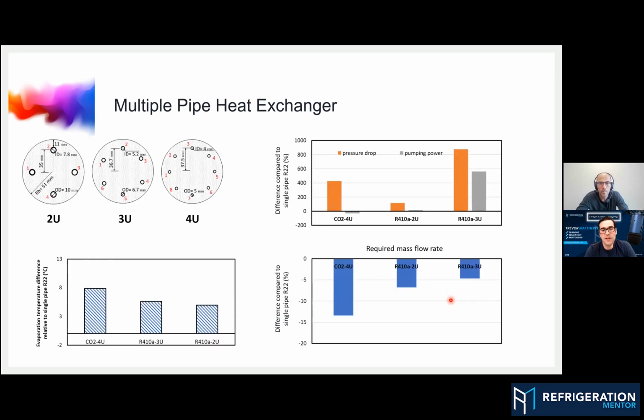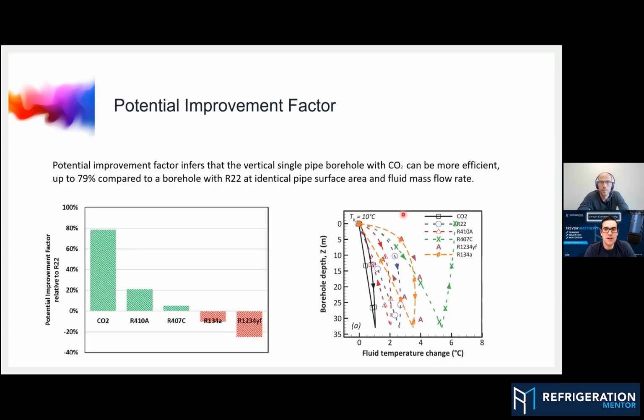Can you talk about the three things you said for pressure loss, or temperature change? I know one was friction. Yeah, friction, acceleration, and gravity are the three terms that we use to calculate the total pressure drop. So basically, the total pressure drop is created based on those three terms: acceleration, friction, and gravity. It's not only friction.